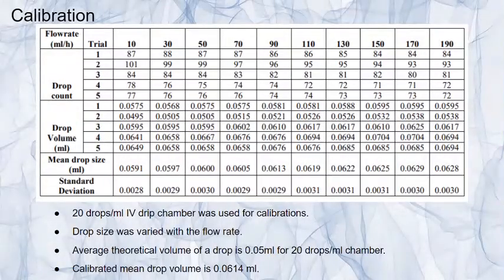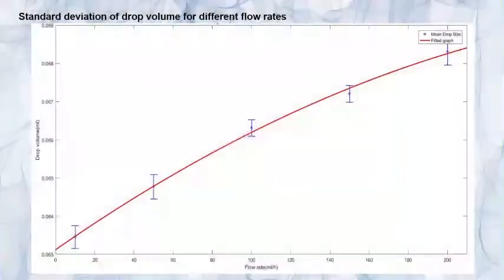A Perfusor compact infusion pump was used to send 5 ml of water at a fixed flow rate. The theoretical average drop volume is 0.05 ml. But according to the result of the above calibration, the average drop volume changes with flow rate. The average size of a drop was calculated as 0.0614 ml using the above calibration.